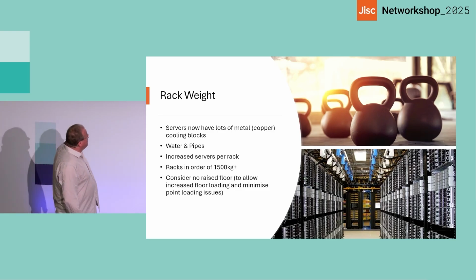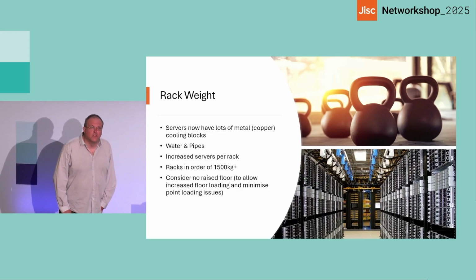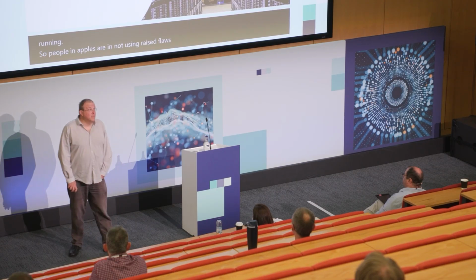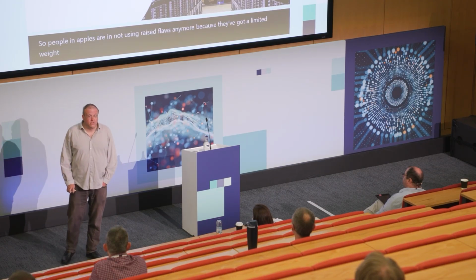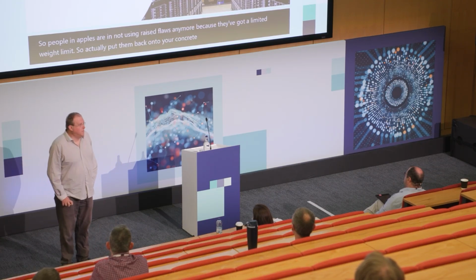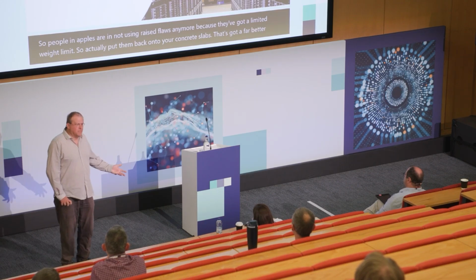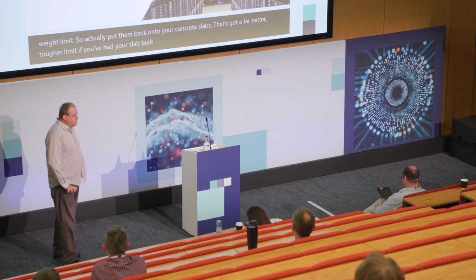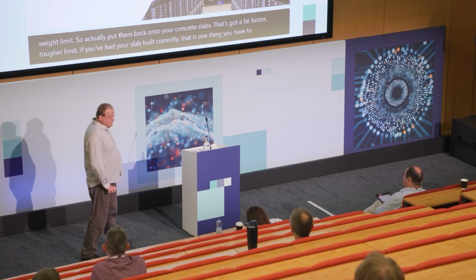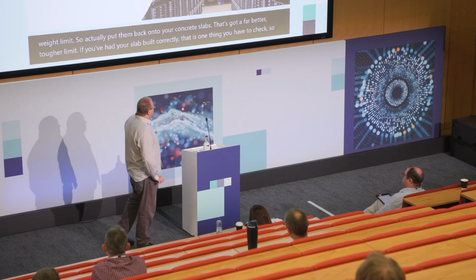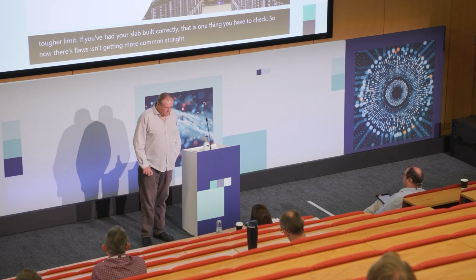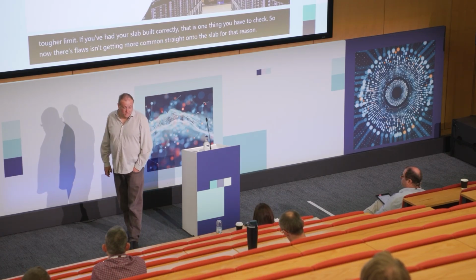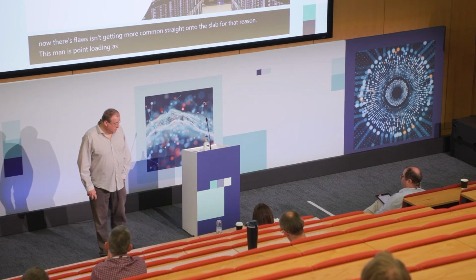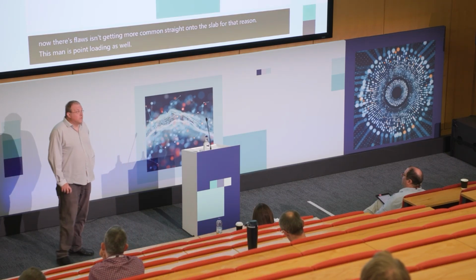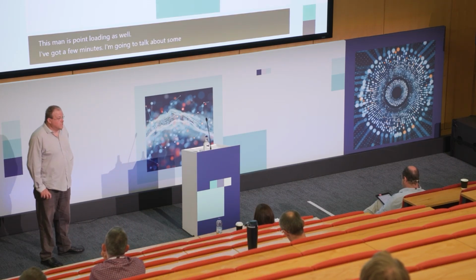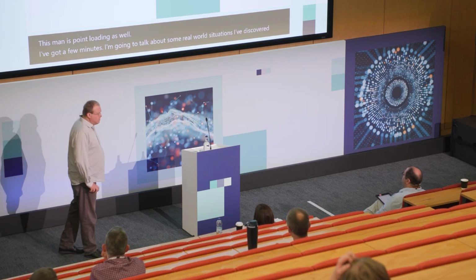So people are now considering not using raised floors anymore because they've got a limited weight limit. So actually put them back onto your concrete slabs. That's got a far better, tougher limit, if you've had your slab built correctly. That is one thing you have to check. So now putting racks straight onto the slab is getting more common for that reason. It's managing point loading as well.